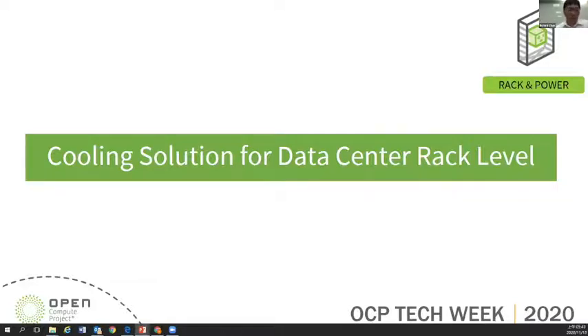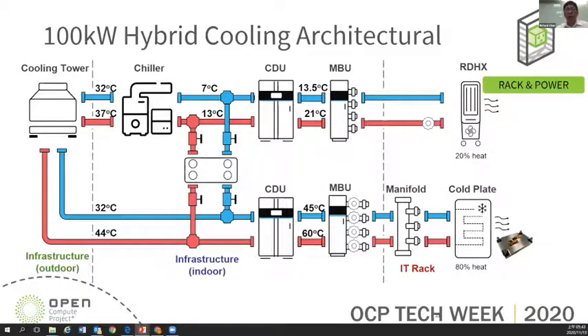Good afternoon. Then I will present a cooling solution. We propose a cooling solution for a 100 kilowatt per rack system. The cooling system is hybrid, including liquid cooling and air cooling. The major heat, such as from CPU or GPU, is dissipated through the cold plate and then to the cooling tower. The other minor heat, maybe 20% to 30%, is dissipated by the rear door heat exchanger and through the chiller. So this is better for PUE performance.